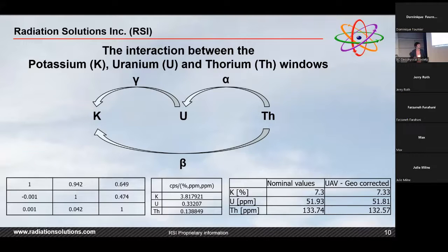And yeah, we're pretty close, pretty spot on. That's always a good check, because if you see a big difference, then it means something went wrong. Either you had a bad measurement, you didn't take the right measurement into account, or the crystal might have cracked in between. You have all sorts of issues that you can spot right there.